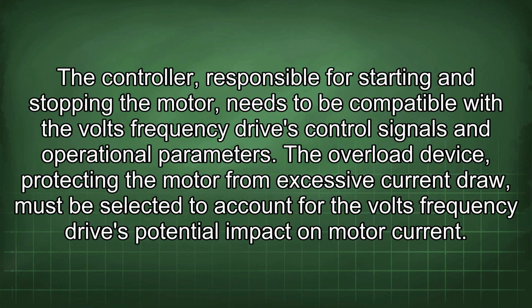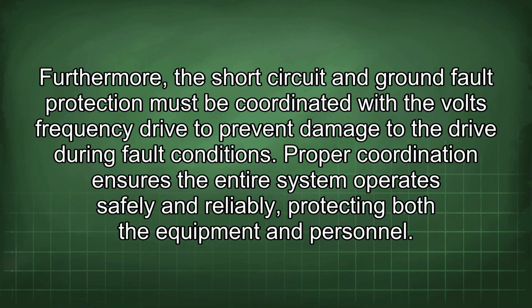The controller, responsible for starting and stopping the motor, needs to be compatible with the volts-frequency drive's control signals and operational parameters. The overload device, protecting the motor from excessive current draw, must be selected to account for the volts-frequency drive's potential impact on motor current. Furthermore, the short circuit and ground fault protection must be coordinated with the volts-frequency drive to prevent damage to the drive during fault conditions. Proper coordination ensures the entire system operates safely and reliably, protecting both the equipment and personnel.